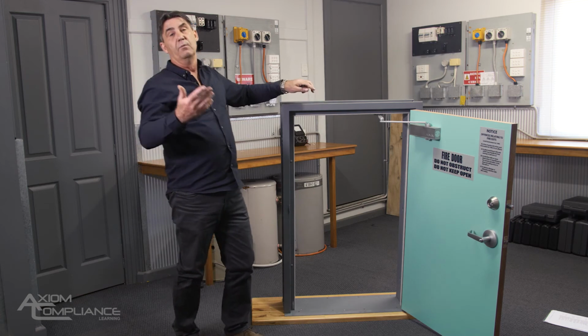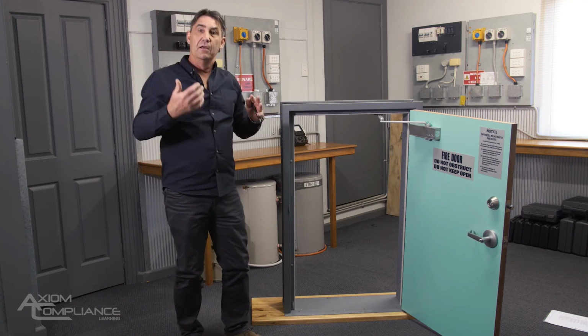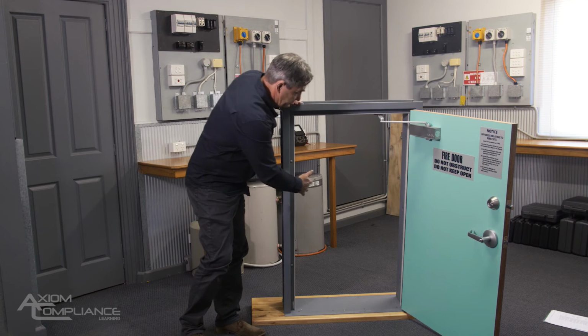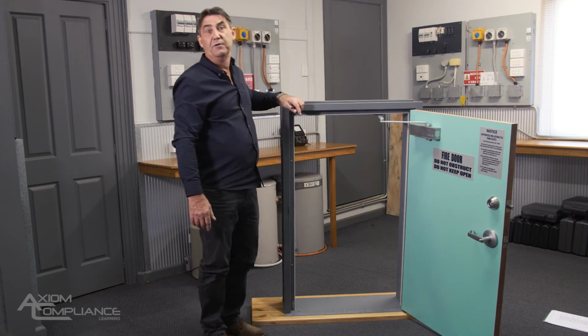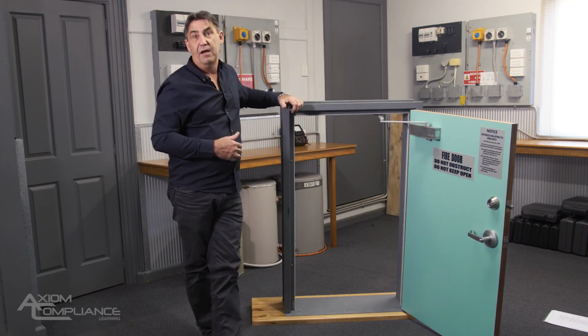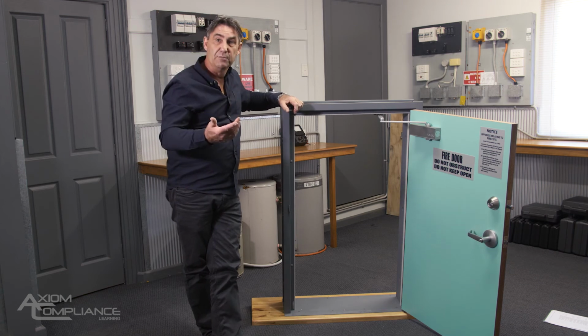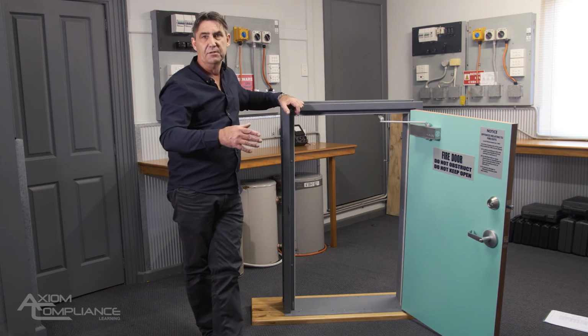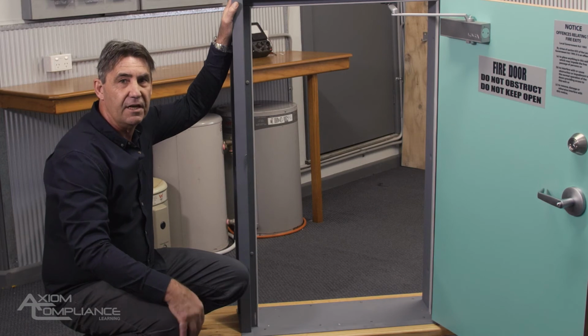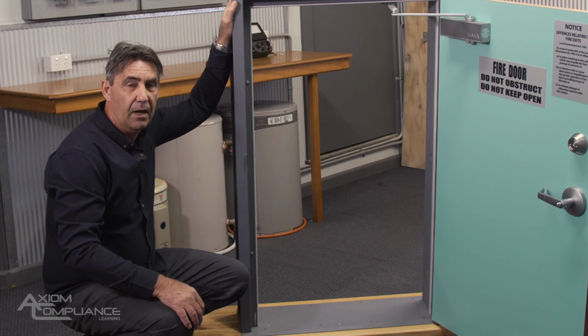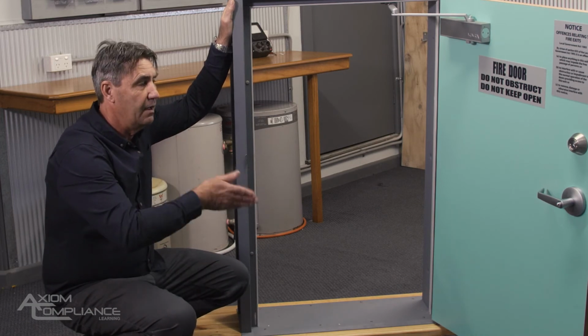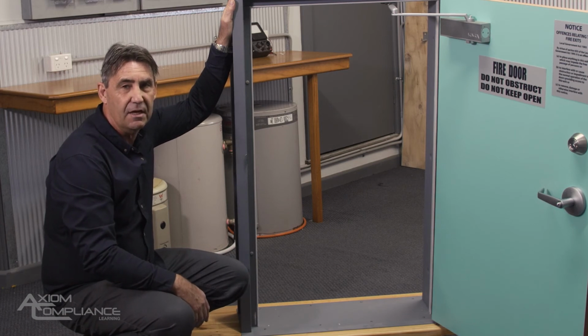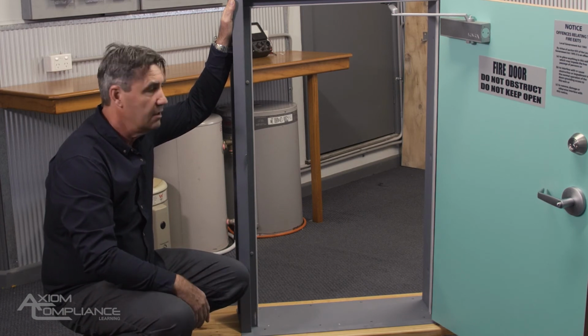And once again, we don't have to pull the door frame out and seal it. We can drill up to a 25mm hole into the frame of a door and we can fill it with fire rated foam. So you might need to get a specialised person to do that, but there are options. Okay, so that takes care of the frame of the door. We just need to look at a couple of warping factors and stuff like that when the door's closed.